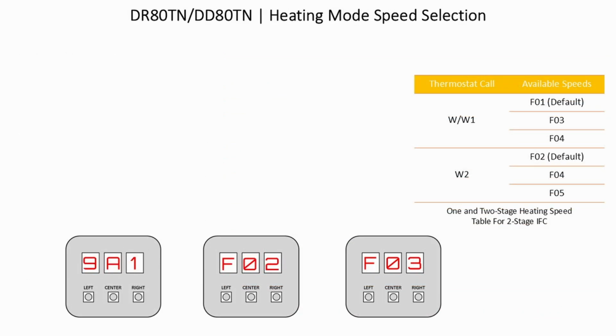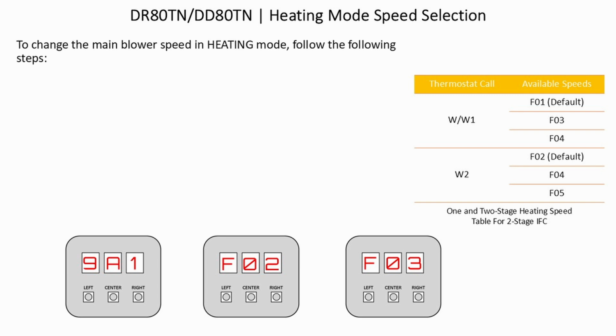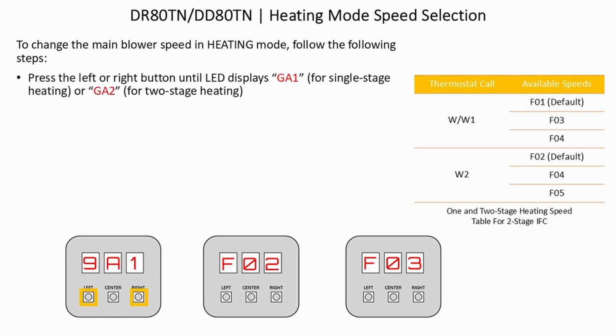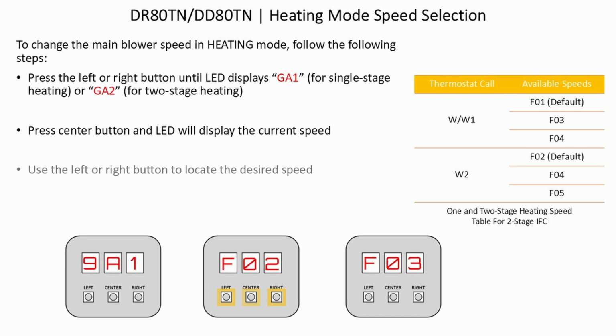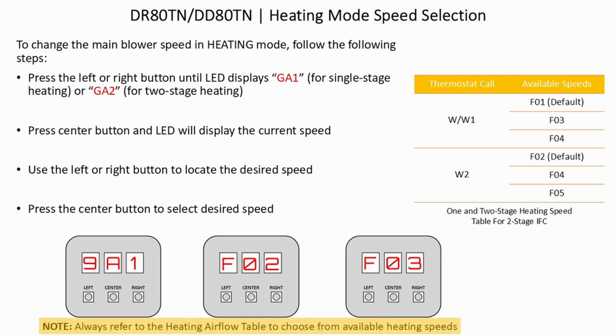DR80TN, DD80TN, heating mode speed selection. To change the main blower speed in heating mode, follow these steps. Press the left or right button until the LED displays GA1 for single-stage heating or GA2 for 2-stage heating. Press the center button and the LED will display the current speed. Use the left or right buttons to locate your desired speed. Press the center button to select the desired speed. WW1, F01 is default. W2, F02 is default. Always refer to the heating airflow table to choose from the available heating speeds.